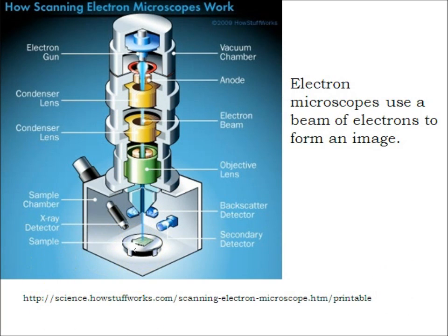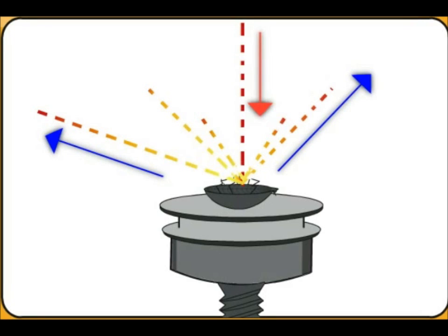This can cause a problem. A lot of things we look at in our microscopes are non-conductive. And as you found out, hopefully with the TM1000, if something is non-conductive, it can actually gather a charge. And then it gives off lots of electrons and all we see is a glow. So let's take a look at what happens when the electron beam hits the specimen and how that ends up making an image on our computer screen.